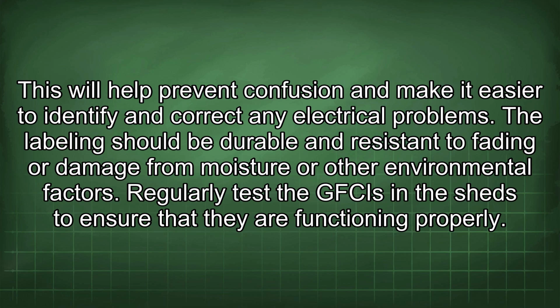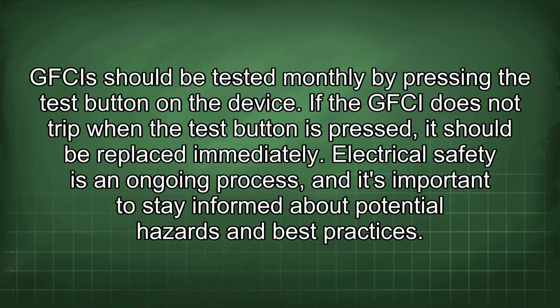Regularly test the GFCIs in the sheds to ensure that they are functioning properly. GFCIs should be tested monthly by pressing the test button on the device. If the GFCI does not trip when the test button is pressed, it should be replaced immediately.